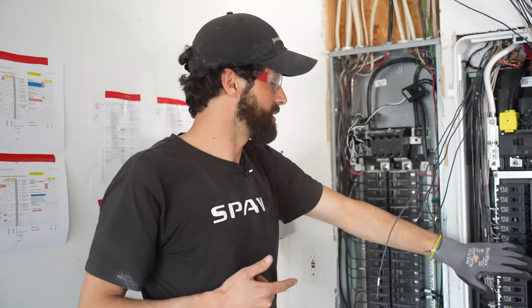Good precaution. We've got a bunch of spare breakers here. I've harvested the GE breakers that we pulled out that are not compatible with Span, and I put all the spares in here. Spares, by code, have to be labeled as such. Every circuit has got to be labeled with a non-occupant specific labeling mechanism. So north, south, east, west is better than Bobby's room, for instance. In addition to that, every circuit must be labeled distinctly from every other circuit. So you can't have lighting circuit, lighting circuit, lighting circuit, lighting circuit. I've seen that so many times. Every label must be distinct, non-occupant specific, and spares must be identified.